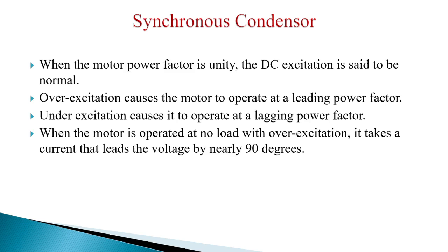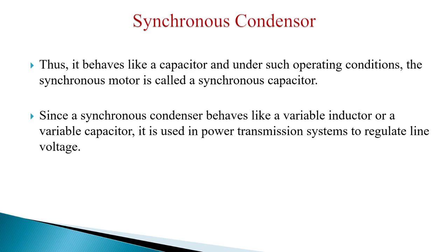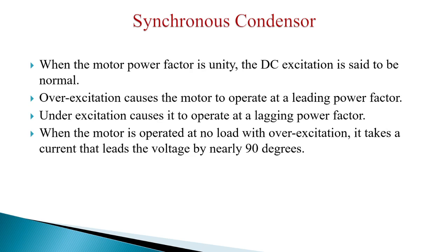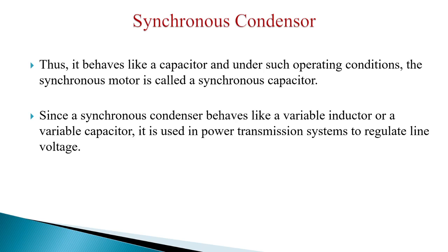When the motor is operated at no load and with overexcitation, it takes a current that will lead the voltage by nearly 90 degrees. So it will behave like a capacitor, and under such operating conditions, the synchronous motor is called a synchronous capacitor. For a pure capacitor, we know that current will lead the voltage by 90 degrees.